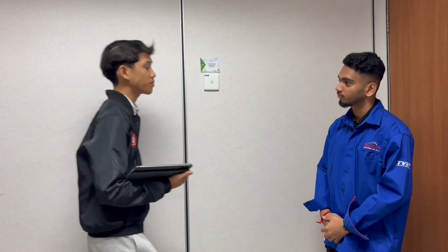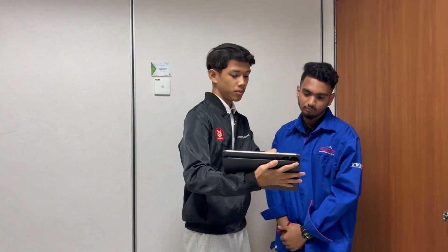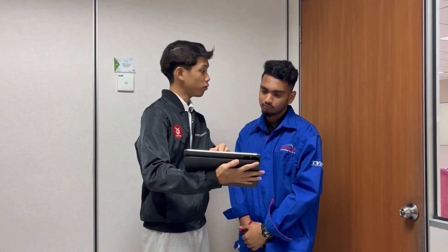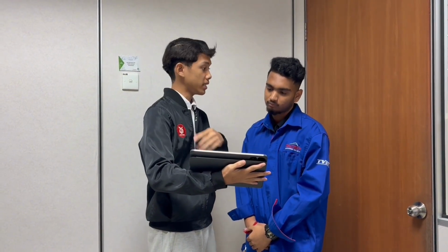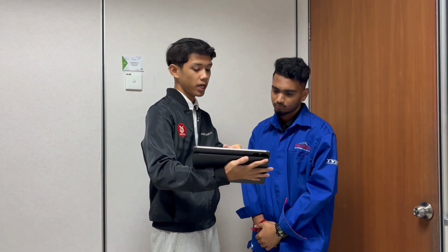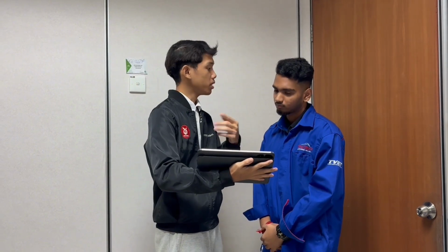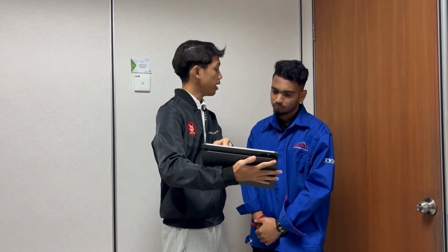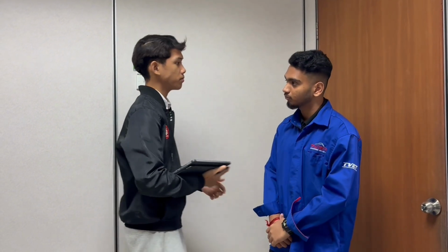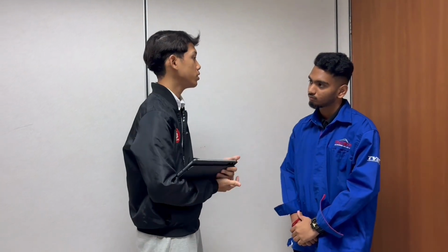Sure, what happened? The monitor shows a blood pressure reading of 145/95. When I check manually, I got 128/82. I repeated the measurement twice and the difference was still there. I see. Was the patient positioned properly when you took the measurements? Yes, the patient was resting and the cuff was positioned correctly.